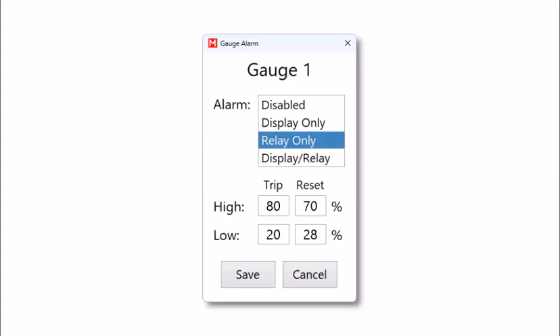The relay alarms are about as complicated as the full view bin monitoring system gets. And this is the portion where we would recommend the involvement of an electrician or someone well-versed in electrical wiring. To use the relay port for alarms, you will need to build a custom cable according to the information in the bin monitoring system manual.